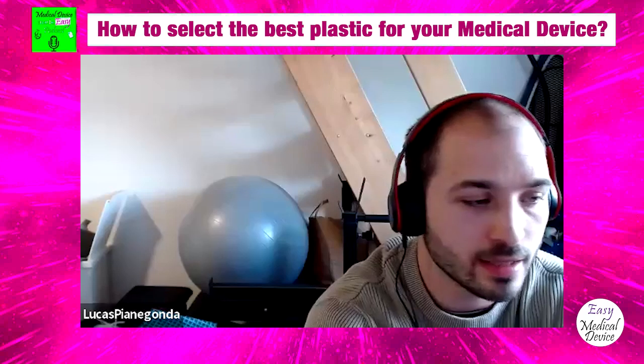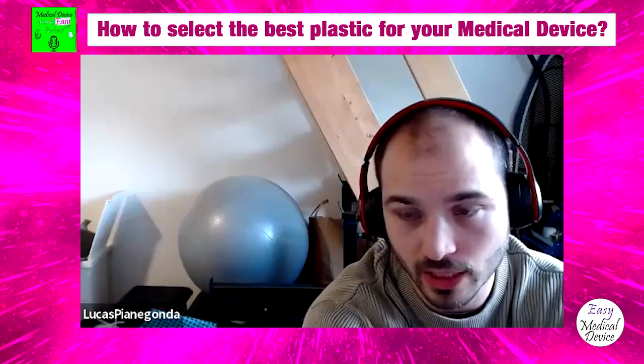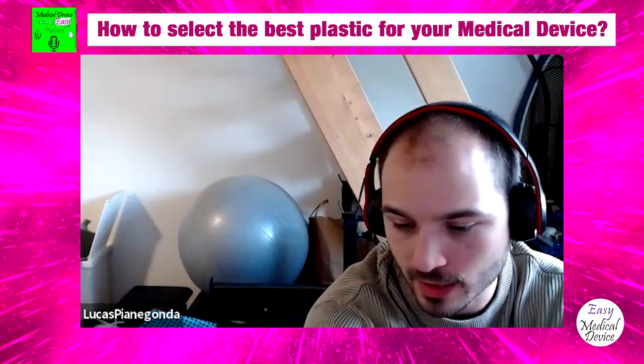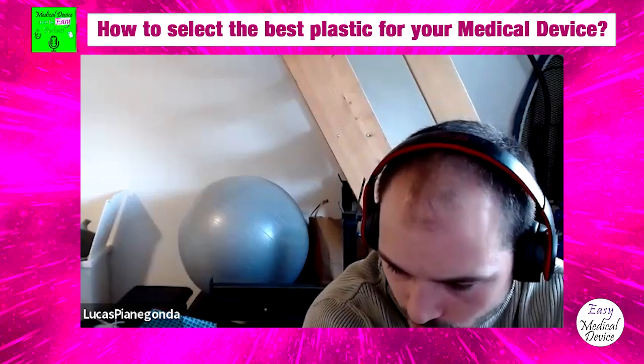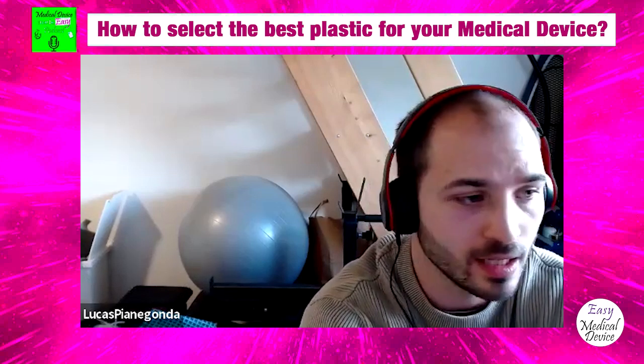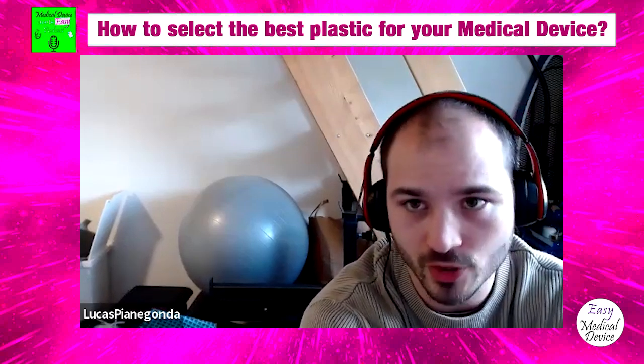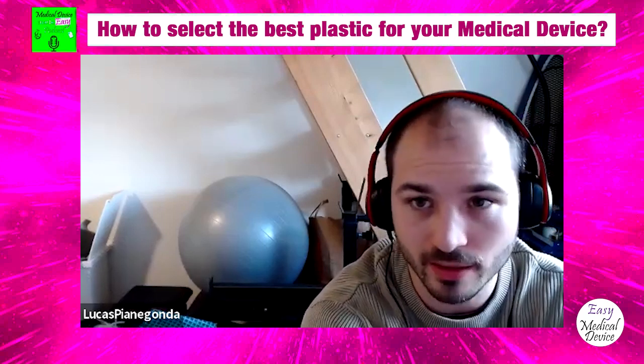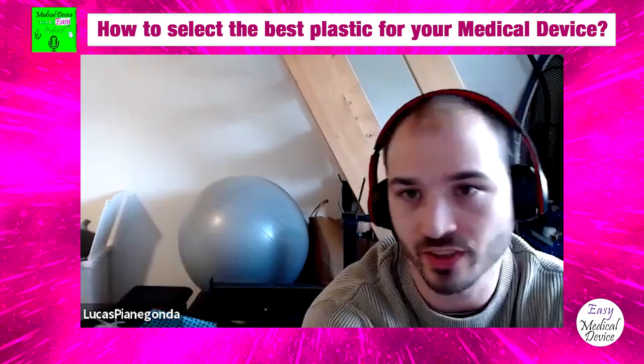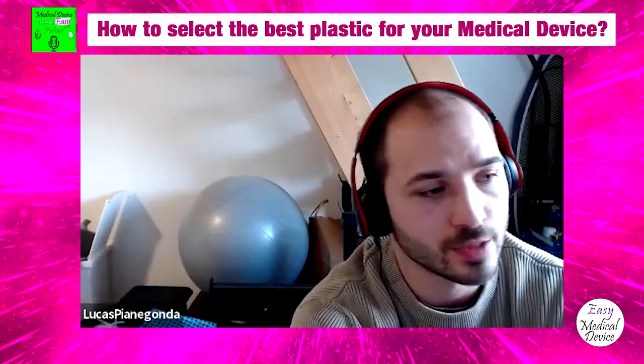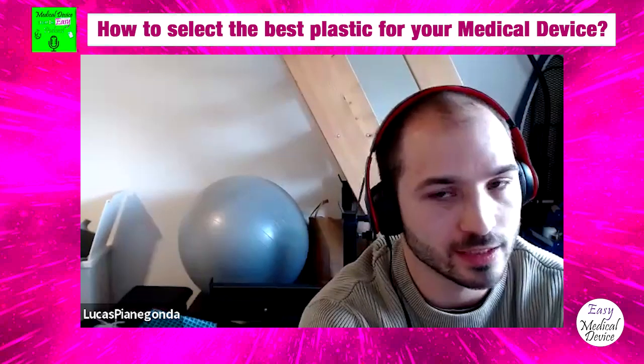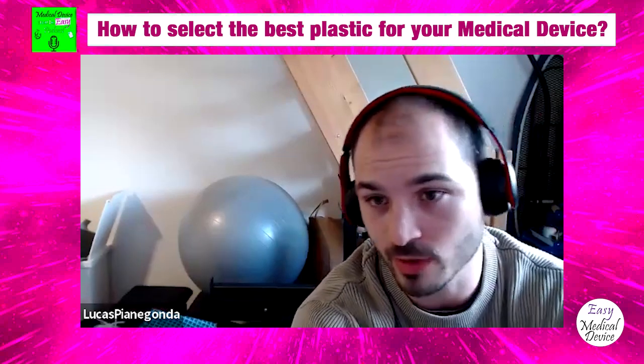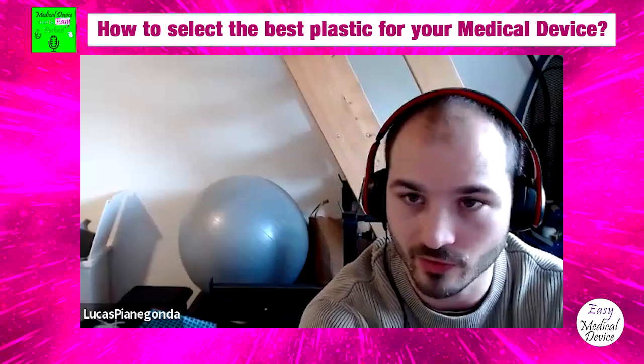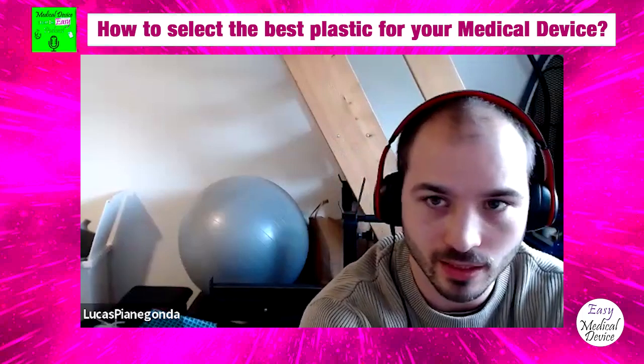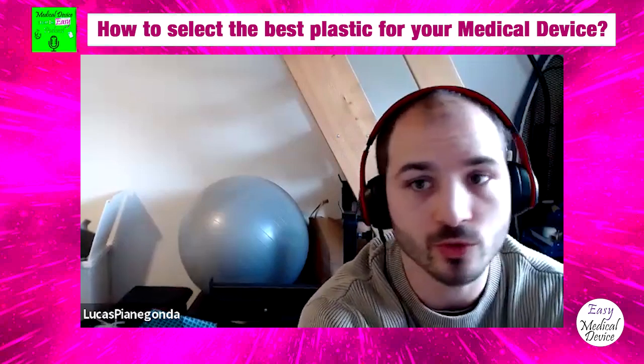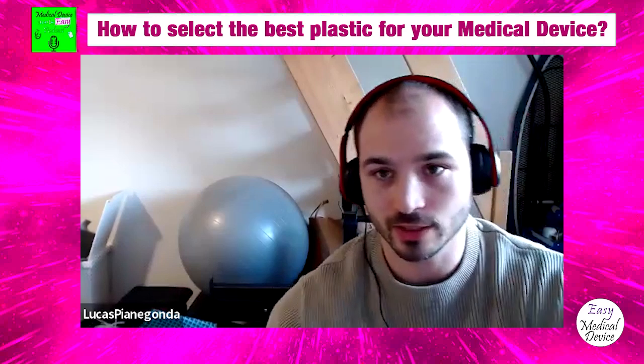plastics? I mean, there are certain substances that are outright banned. So there are substances like polybrominated flame retardants that you just cannot use. But it's usually the exception that you really cannot use something because it's banned. If you cannot use something, it's usually very difficult to get it because no one can sell it to you. So what happens more often is the question: can you produce a safe and effective device with this plastic? And if you can answer the question and you have proof for it, there is seldom the FDA or the notified body telling you, no, you cannot use this. You just have to prove that it's safe and effective.